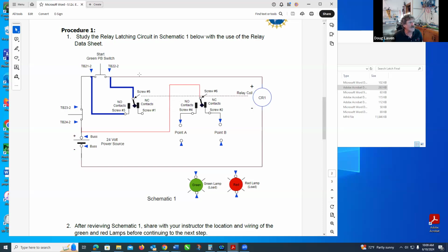So what do you see here now that makes this latch? What's unique about this is the green push button switch. All I've done is taken that set of control contacts and put them in parallel. Right now, it's normally open, and I have this side tied to here, and this side going nowhere. But when I push the button down, this swings over, and now I have amperage going through here and through here, which energizes this coil.